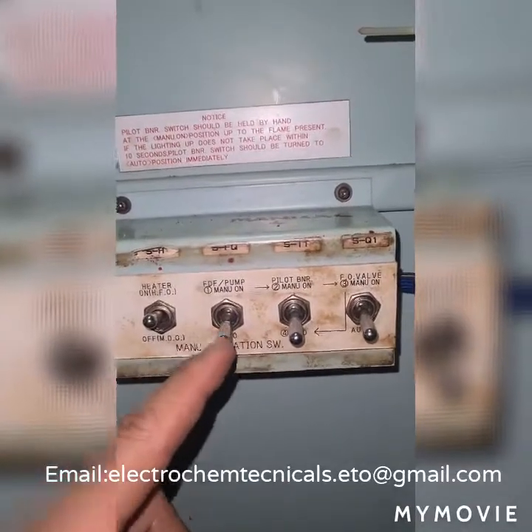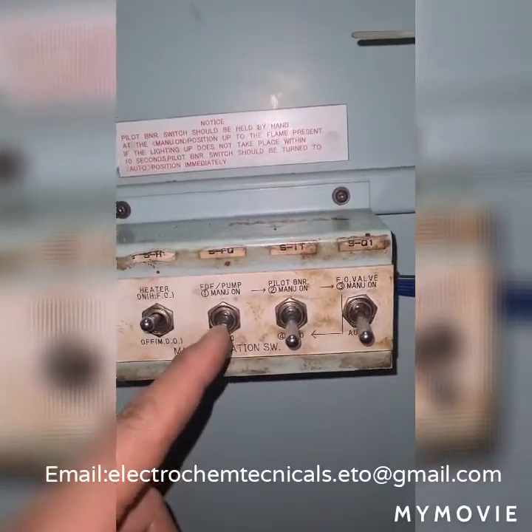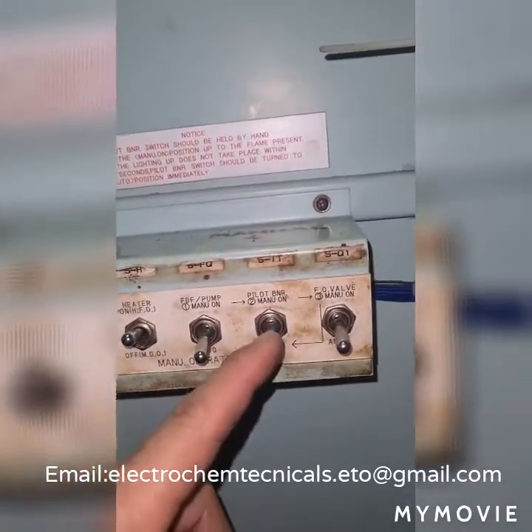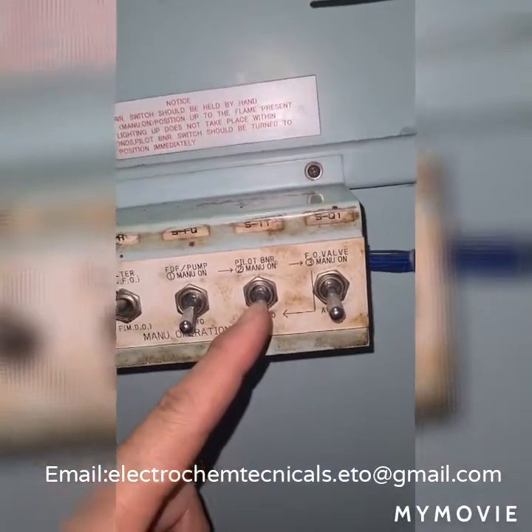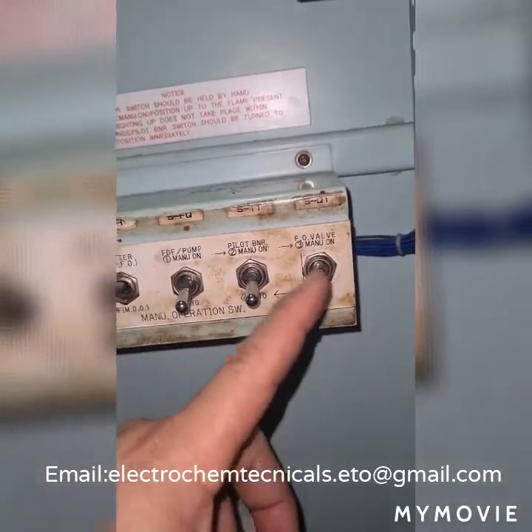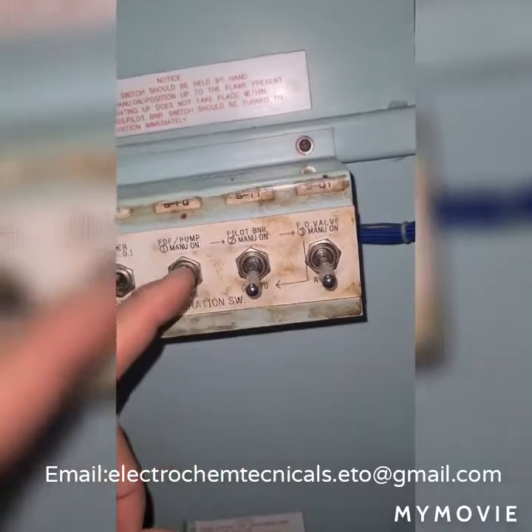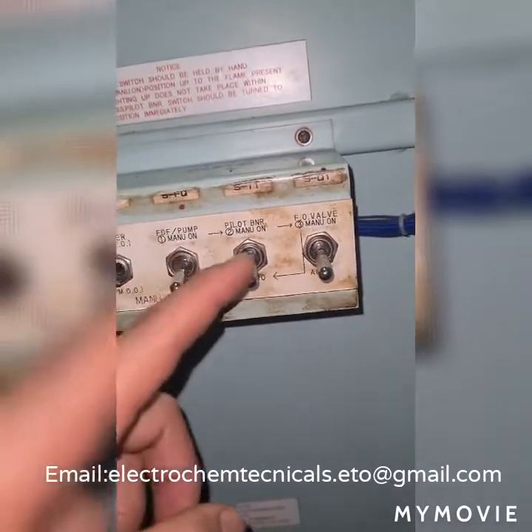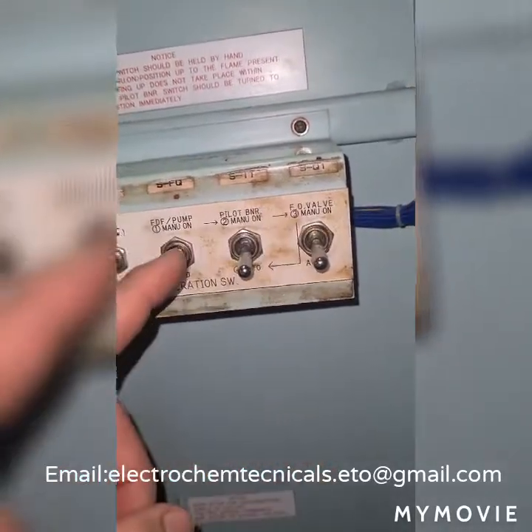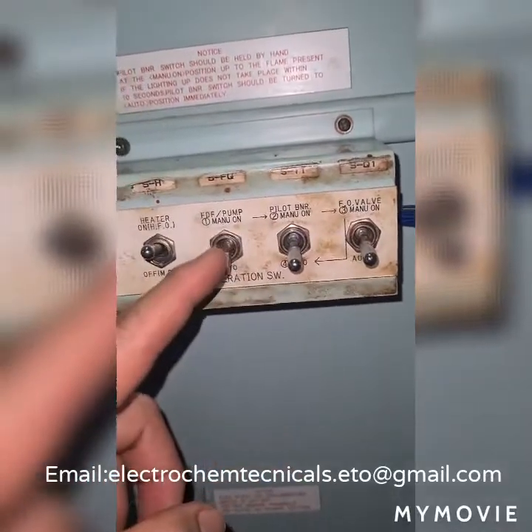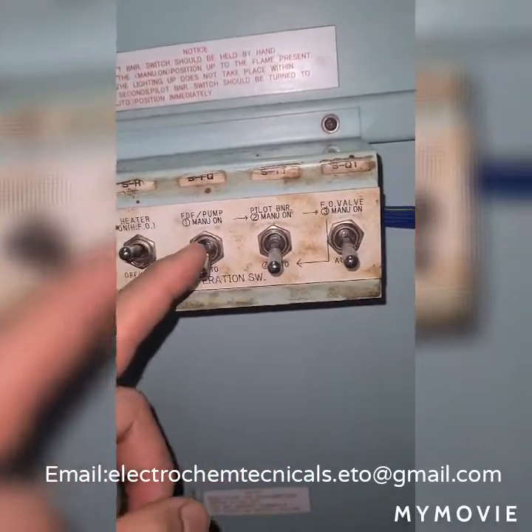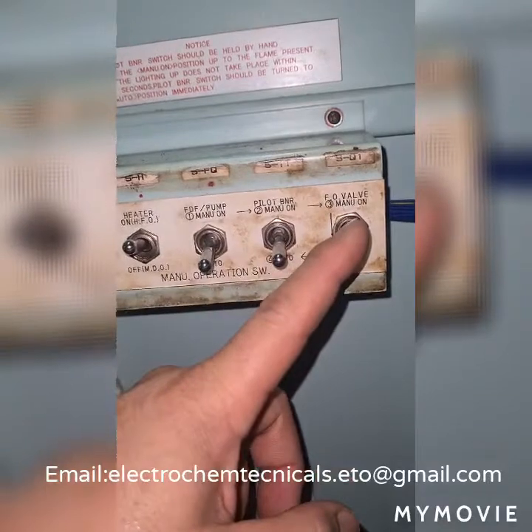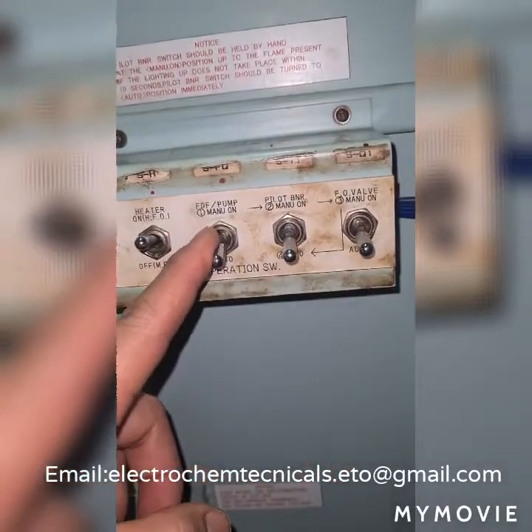It means you operate the forced draft fan, the pilot burner, and the fuel oil valve in auto mode when this is down. But if you put this in the up position, it means you operate the forced draft fan, the pilot burner, and the fuel oil valve in manual mode.